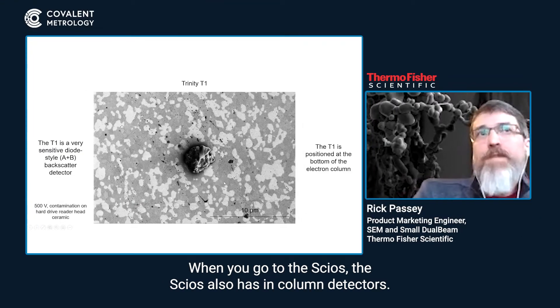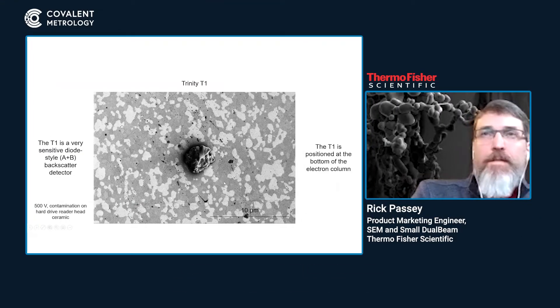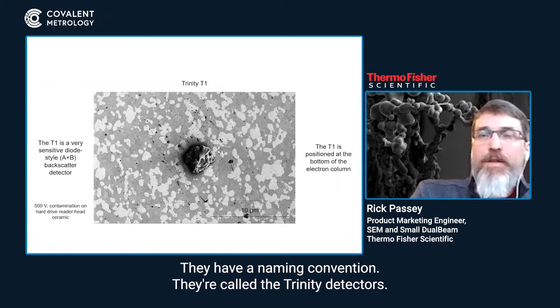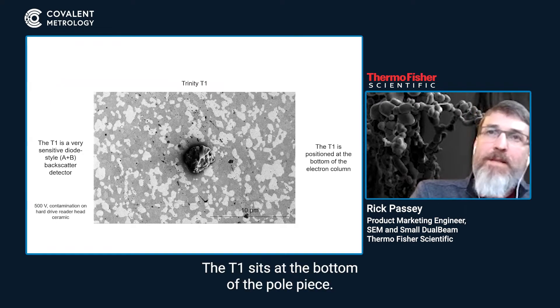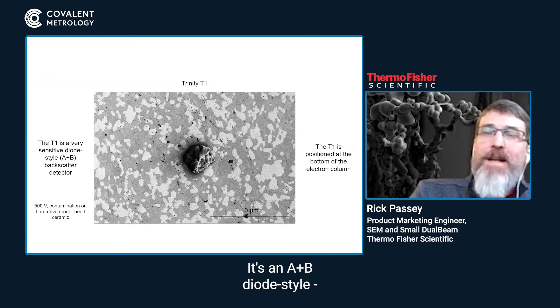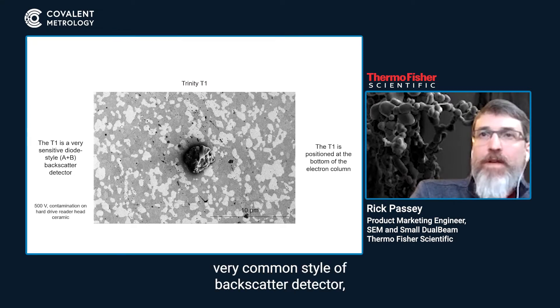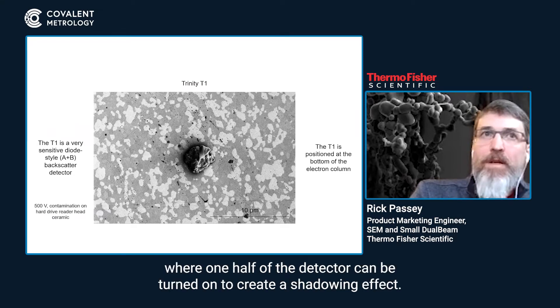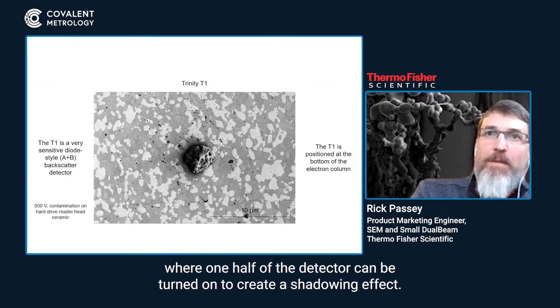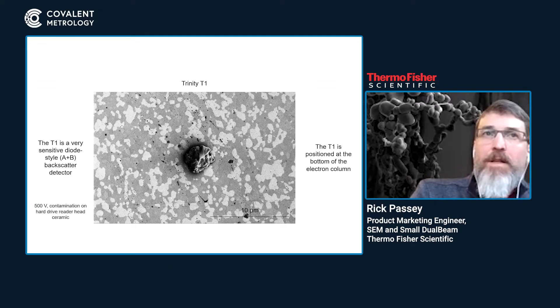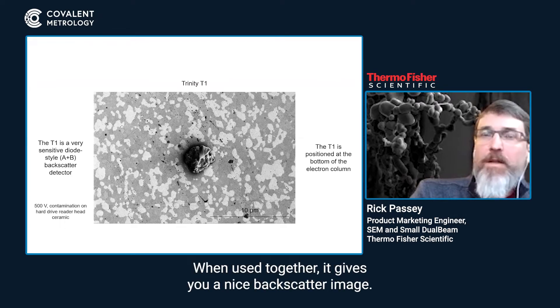When you go to the Scios, it also has in-column detectors with a naming convention — they're called the Trinity detectors. The T1 sits at the bottom of the pole piece. It's an AB diode style, a very common style of backscatter detector where one half of the detector can be turned on to create a shadowing effect, but when used together it gives you a nice backscatter image.